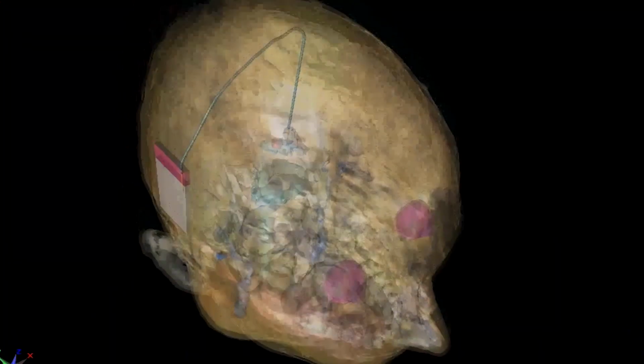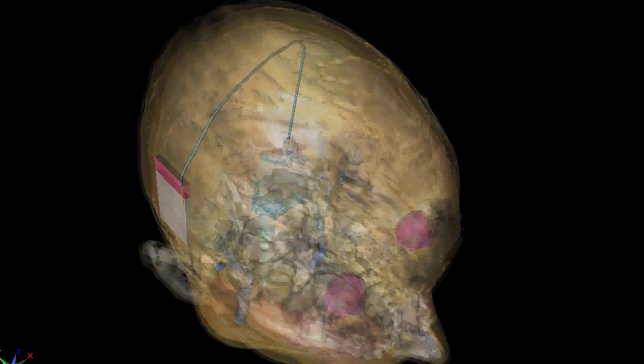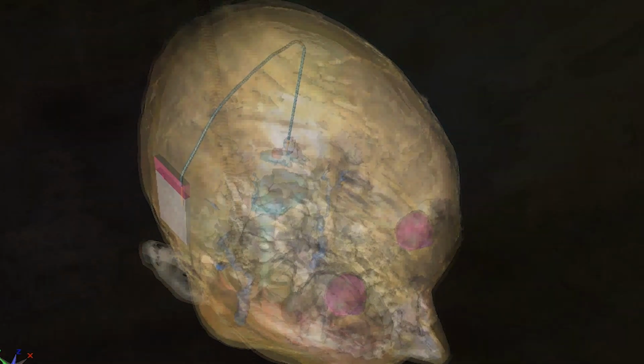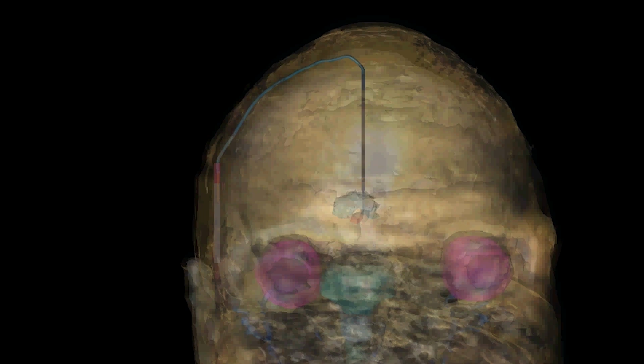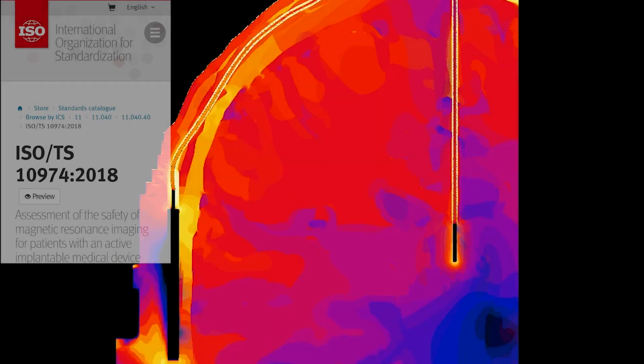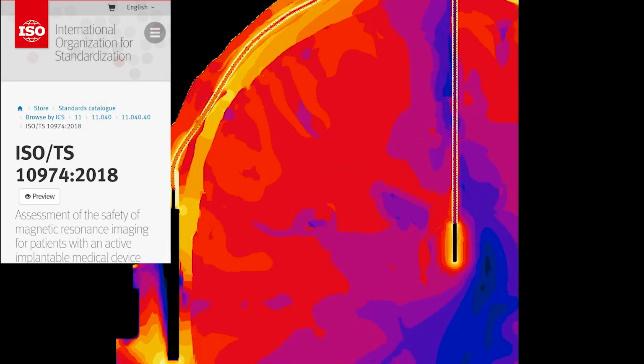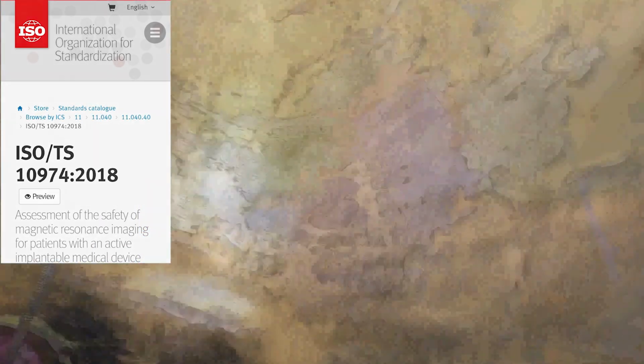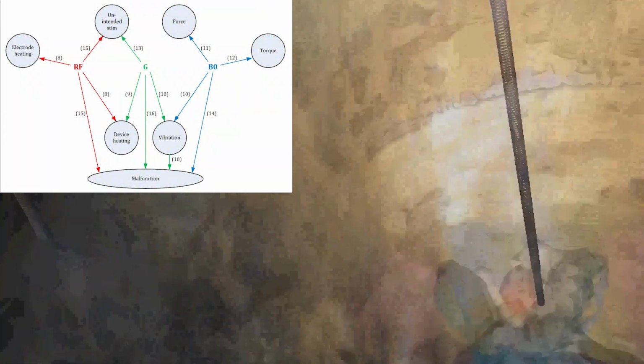Medical implants with long leads pick up energy during an MRI scan. That energy ends up at the electrodes, which dump that energy into the surrounding tissue, and at the lead terminals, creating a voltage spike which can cause a malfunction. The ISO technical specification 10974 tells you how to measure a leaded implant and tell if it's safe. Clause 8 focuses on RF-induced heating, and Clause 15 focuses on RF-induced terminal voltage.